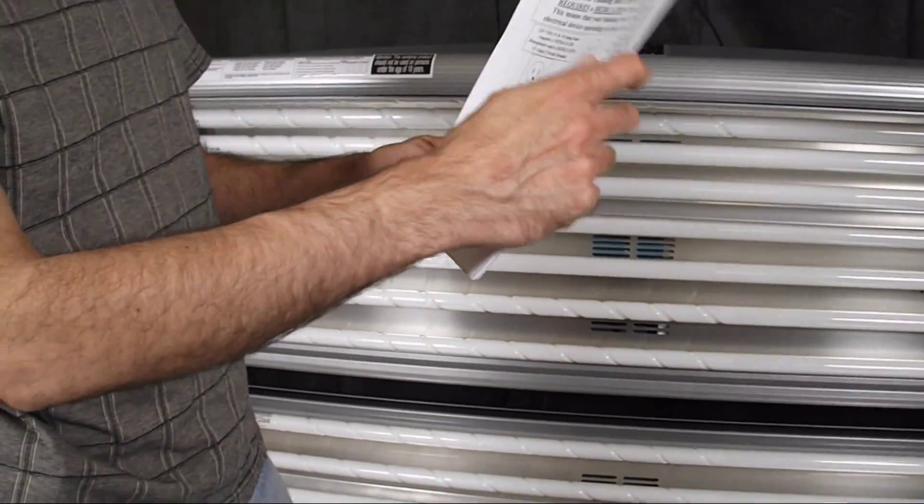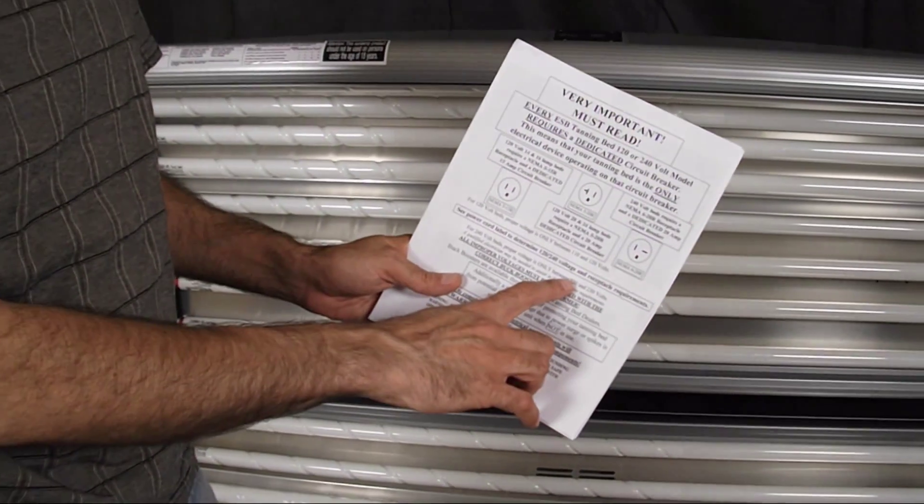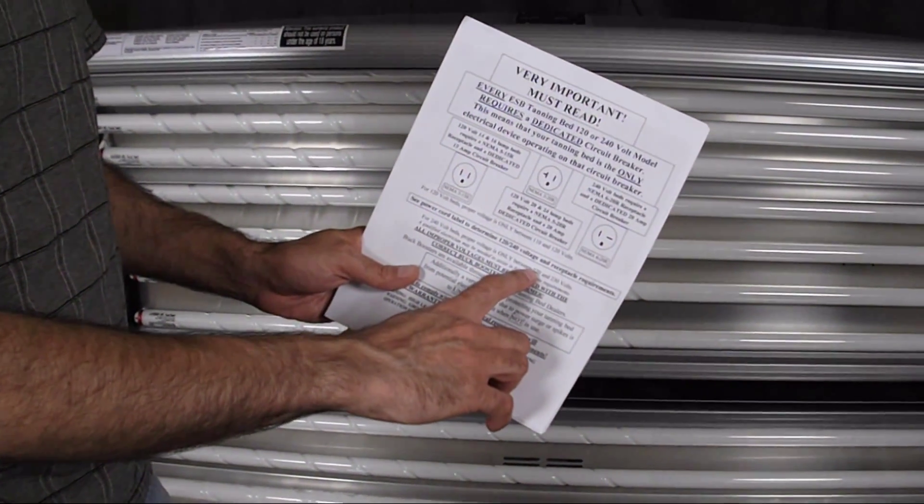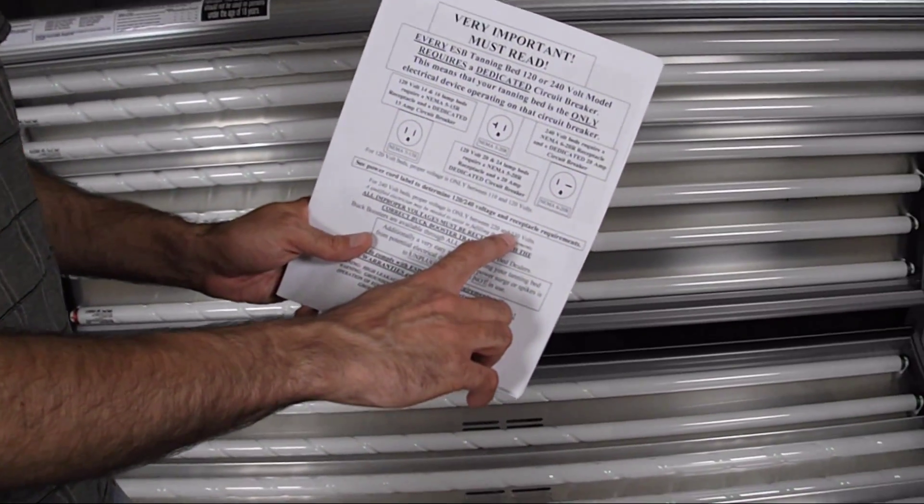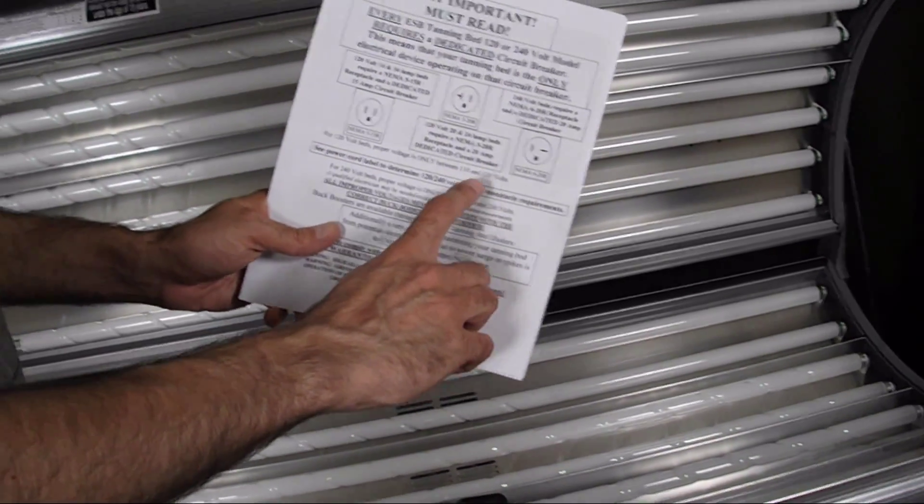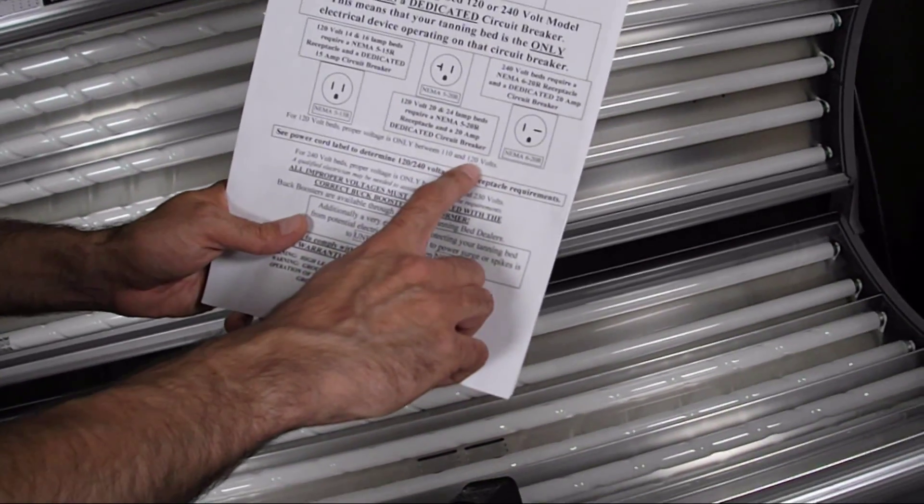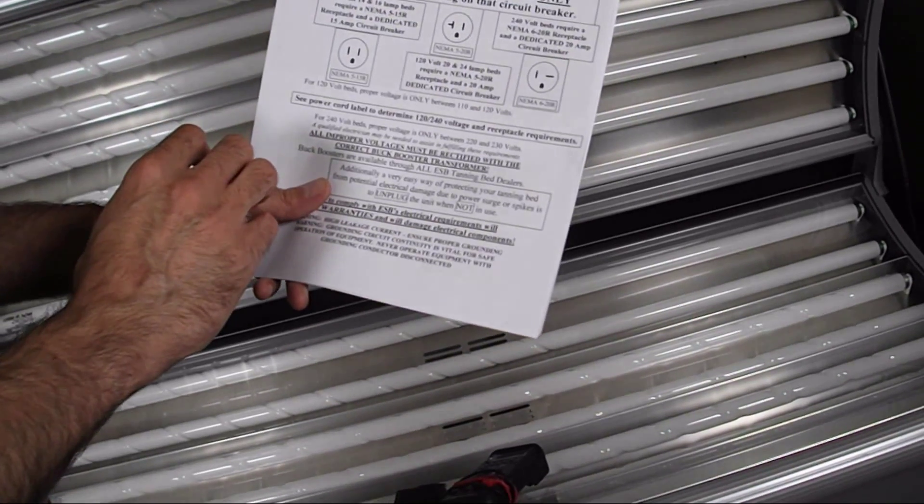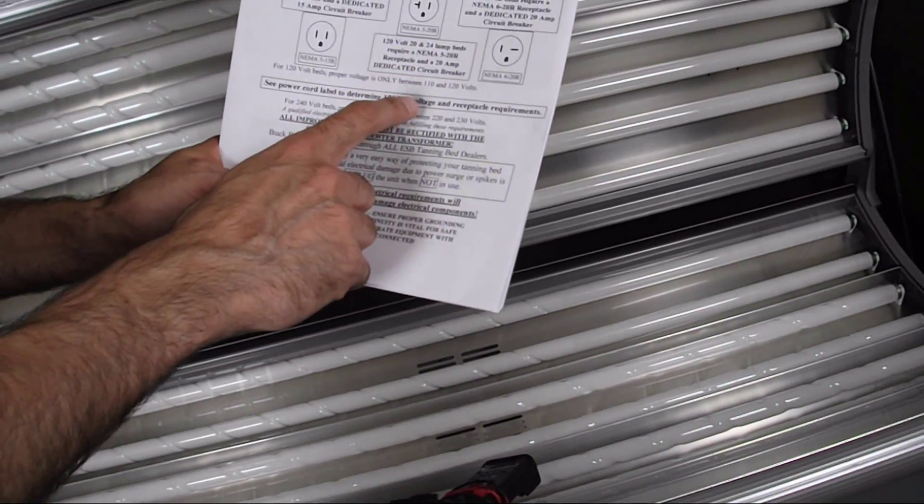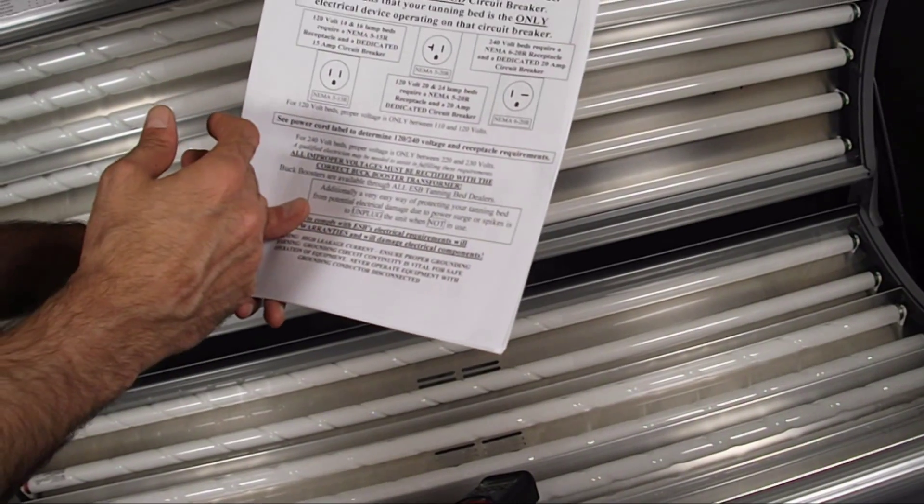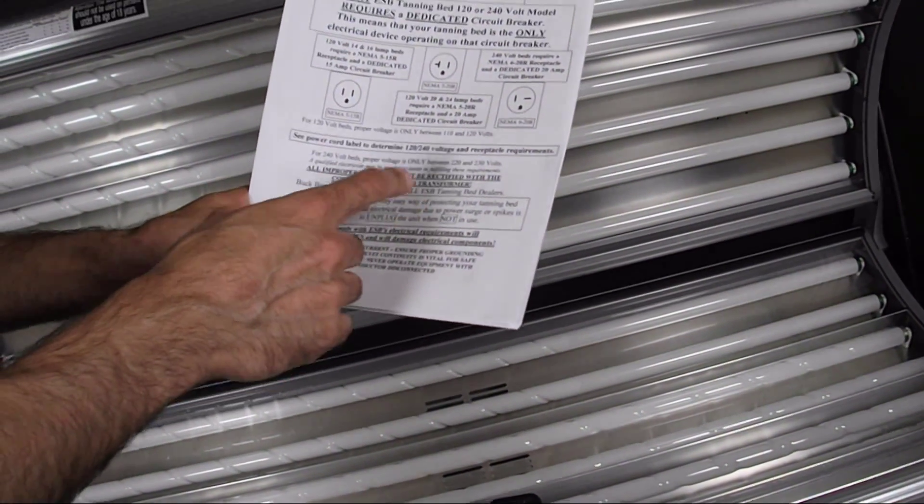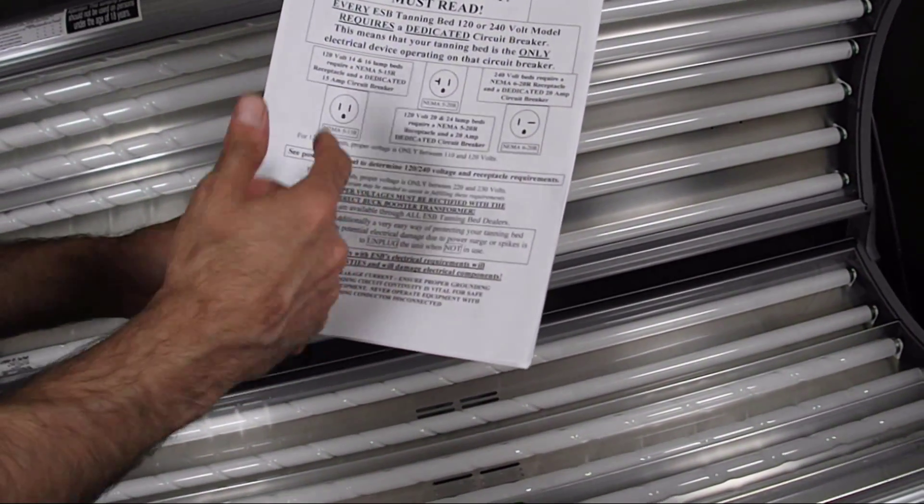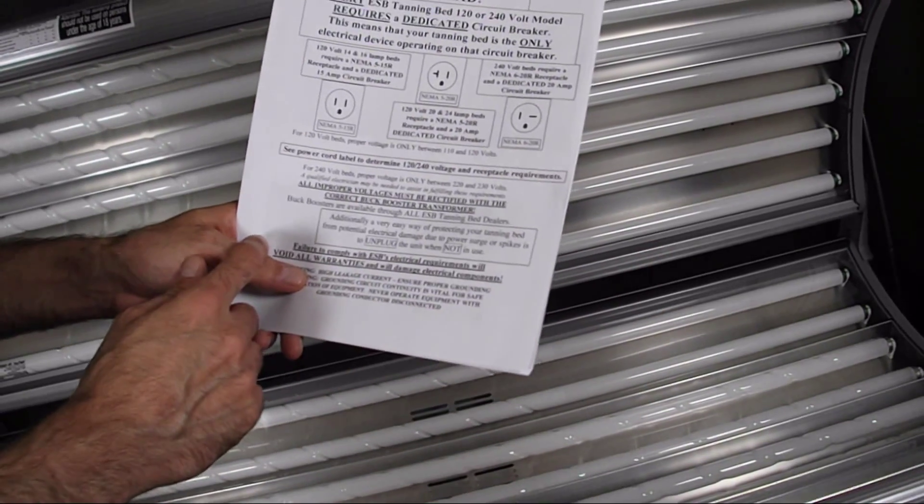A lot of the older beds, especially, would specify only 220 to 230 on the 240 volt side. So you may look into getting a buck booster transformer or something to rectify if you have voltage that is outside of that range.